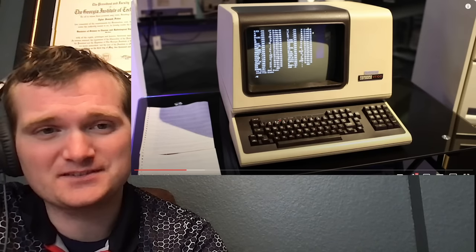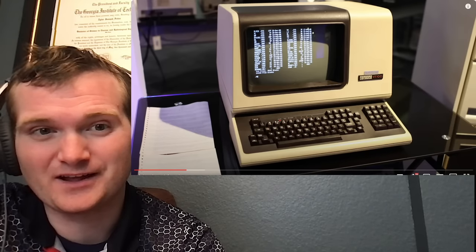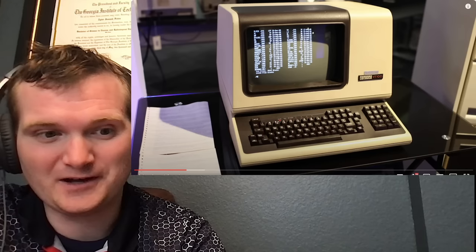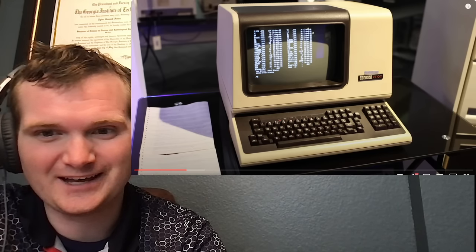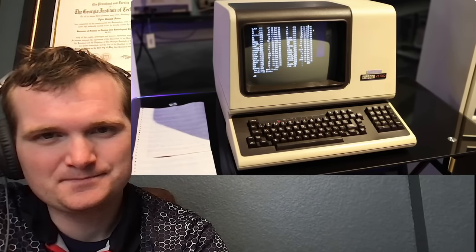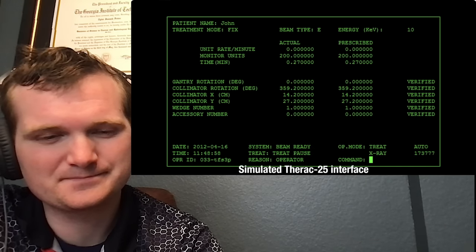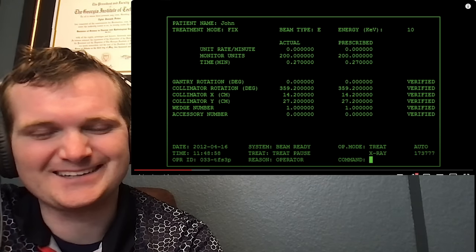As far as adding software, obviously we use a lot of computers now, but I can see how back then there was a lot of fear associated with introducing it — and hopefully it was thoroughly reviewed. In 1983, AECL performed a safety analysis on the new machine and started selling the Therac-25 to excited customers. This state-of-the-art device was in high demand. However, left out of that 1983 analysis was any interrogation of the software that ran these complicated devices.